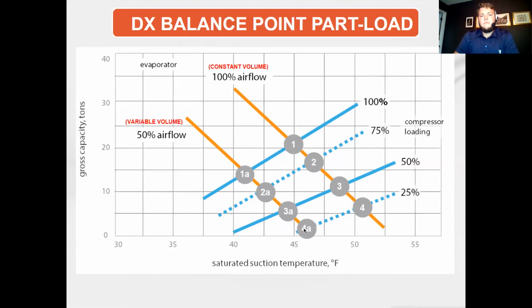You can see point 4A now with 2 compressors running, or 3A with two compressors running. The suction temperature is still close to the design point, and VAV units for that reason are inherently going to take care of humidity better than a constant volume system will. So we've seen a lot of single zone VAV nowadays because of this.